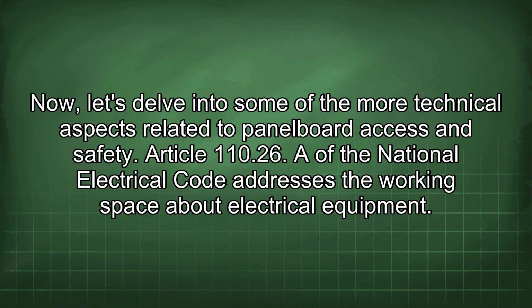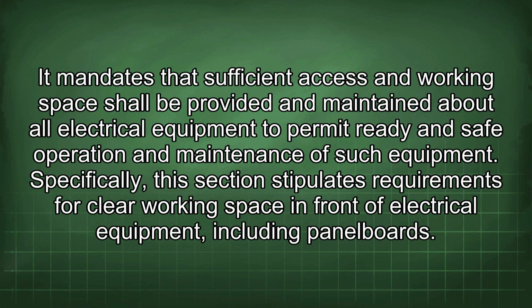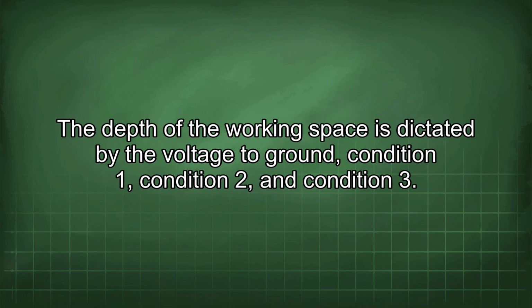Article 110.26 of the National Electrical Code addresses the working space about electrical equipment. It mandates that sufficient access and working space shall be provided and maintained about all electrical equipment to permit ready and safe operation and maintenance of such equipment. Specifically, this section stipulates requirements for clear working space in front of electrical equipment, including panel boards. The depth of the working space is dictated by the voltage to ground, Condition 1, Condition 2, and Condition 3.